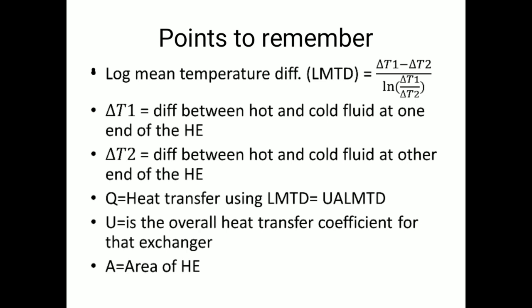LMTD helps to determine the heat transfer — more is the LMTD, more is the heat transfer. The LMTD is given by delta T1 minus delta T2 divided by ln(delta T1 / delta T2), where delta T1 is the difference between the hot and cold fluid at one end of the heat exchanger, and delta T2 is the difference at the other end.